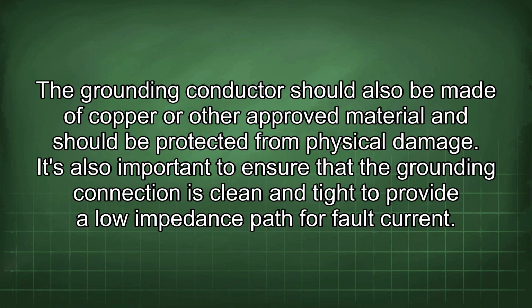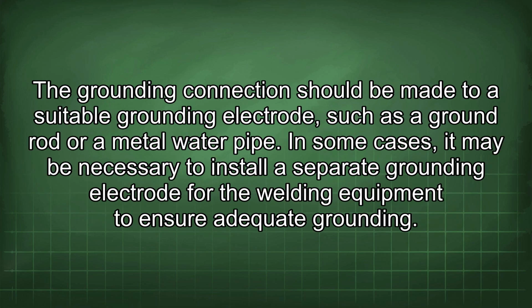The grounding conductor should also be made of copper or other approved material and should be protected from physical damage. It's also important to ensure that the grounding connection is clean and tight to provide a low impedance path for fault current. The grounding connection should be made to a suitable grounding electrode, such as a ground rod or a metal water pipe.